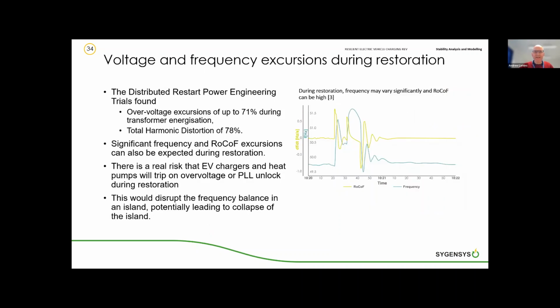Then we consider the case of restoration, as Andrew mentioned earlier. Now, there's been a big project running by ESO called the Distributed Restart Power Engineering Trials, and this is in collaboration with other network operators and transmission owners. And some of the published results from this study show that when energizing network from the LV side for the first time, you can get overvoltage excursions of up to 71% during transformer energization, and with total harmonic distortion up to 78%. So these are very high levels of distortion.